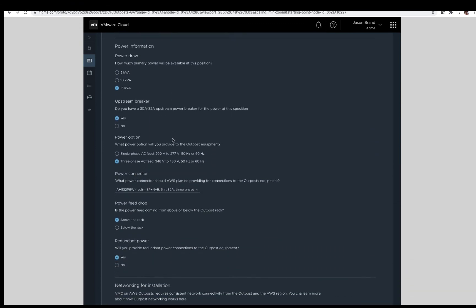Moving on to power information. Power draw. How much primary power will be available at the rack's position? The supported options for VMware Cloud on AWS Outposts are 5, 10, or 15 kVA, depending on your selected host count. If there is a question on the power draw of your selection, please consult your VMware AWS representative to ensure you select the correct power draw. For today's order, we are choosing 15 kVA. Upstream breaker. Do you have a 30 or 32 amp breaker at this position? Specify yes or no. Power option. Will you provide single or three-phase power at this position? For today's order, we will be selecting three-phase power.